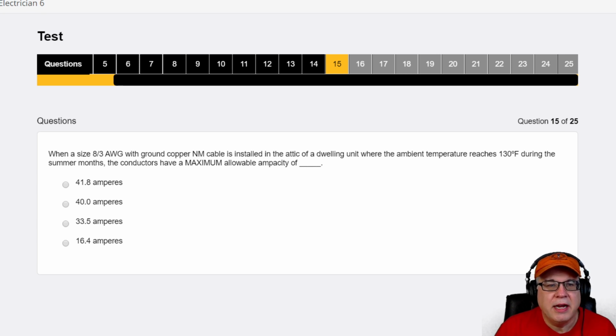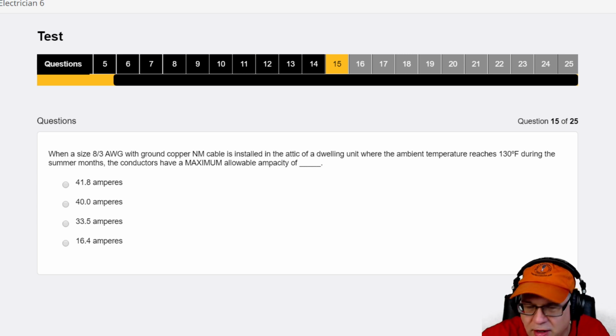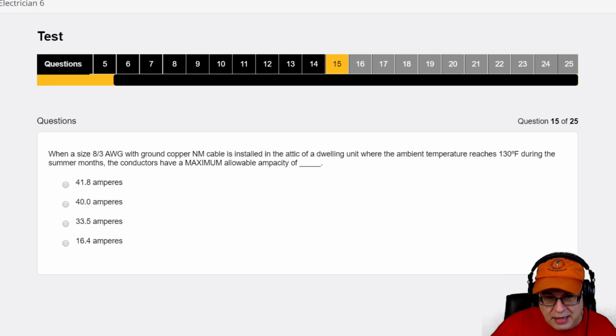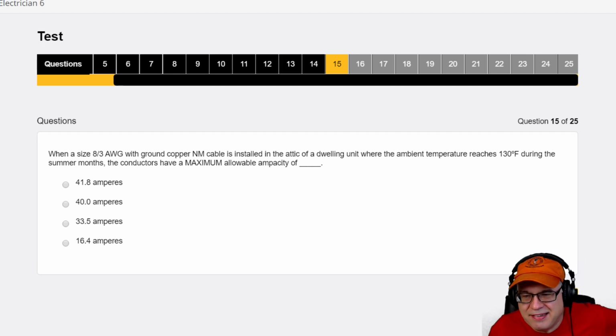Okay, so here we have NMB. We're sticking it in an attic. Now, this is interesting, and this could go either way. I'm going to have to tell you, this could be based on the author, because I'm a stickler for something. It says NM cable, but it doesn't say NMB. So we're going to have to assume maybe that he meant NMB, because it doesn't say NMB in the NEC. Really, it just says it under Part 3 of 334. But we'll assume that it's 90 degree rated insulated conductors. Ultimately it can't exceed the 60 degree. We get it, we understand. But let's see how this works out.